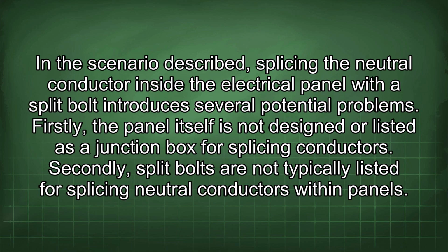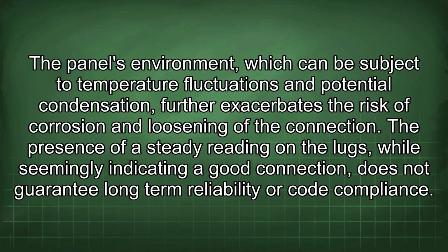In the scenario described, splicing the neutral conductor inside the electrical panel with a split bolt introduces several potential problems. Firstly, the panel itself is not designed or listed as a junction box for splicing conductors. Secondly, split bolts are not typically listed for splicing neutral conductors within panels. The panel's environment, which can be subject to temperature fluctuations and potential condensation, further exacerbates the risk of corrosion and loosening of the connection. The presence of a steady reading on the lugs, while seemingly indicating a good connection, does not guarantee long-term reliability or code compliance.